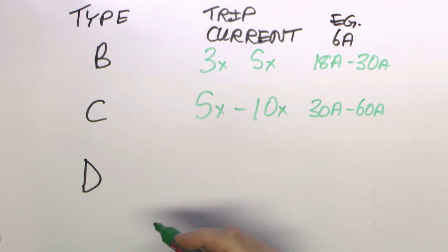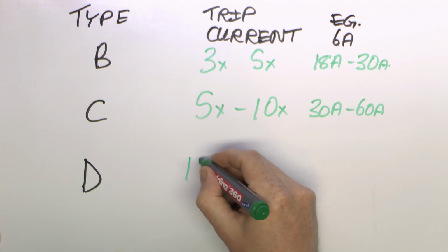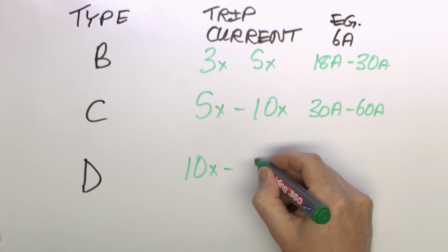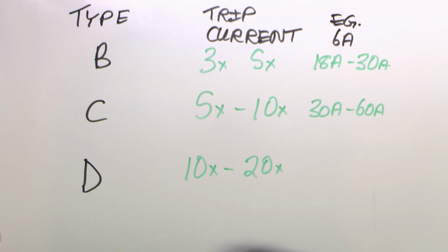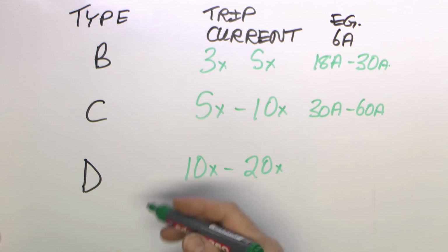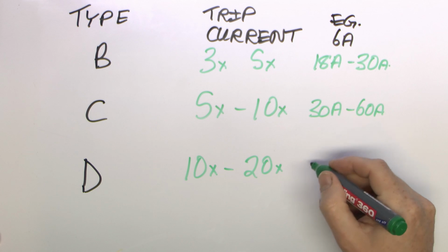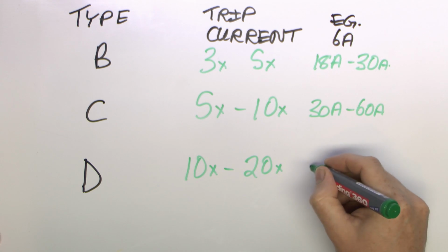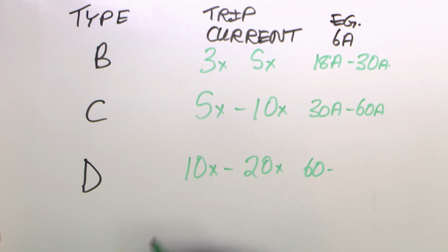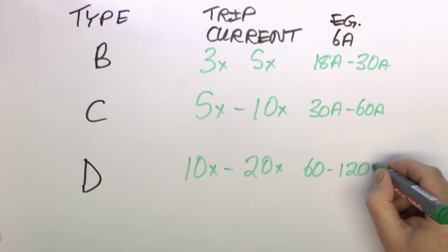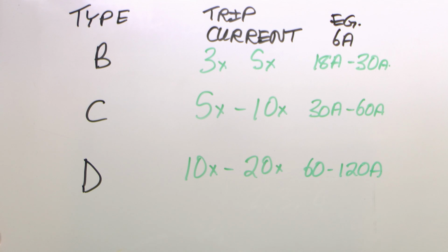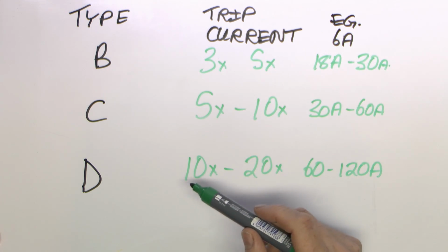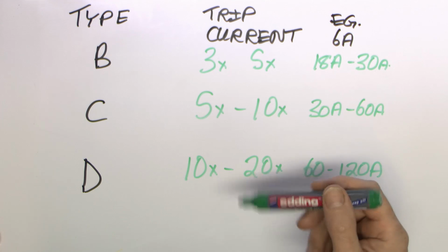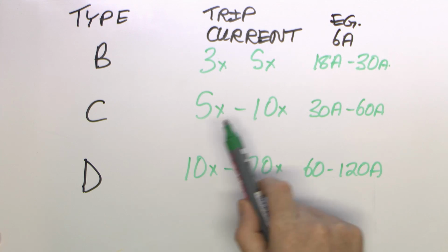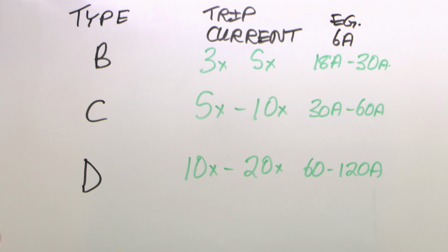And for the Type D, a similar kind of procedure, although the difference is that it's somewhere between 10 times and 20 times. So again, if it was a 6 amp circuit breaker, or a D6, the tripping current would be somewhere in the region of 60 amps at 10 times, to 120 amps at 20 times. These are given as a range because it's not possible to make a magnetic device with a mechanical piece inside which will trip exactly at a particular current, so there's always a range of currents that it will trip at, but it will be somewhere within those parameters.